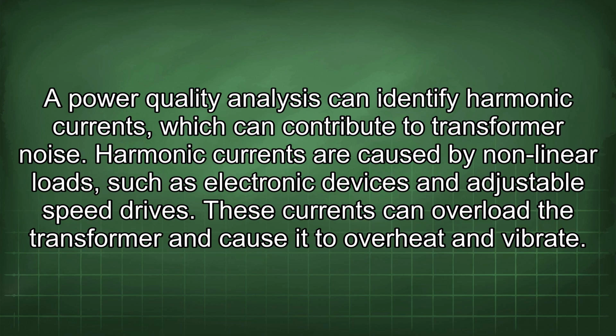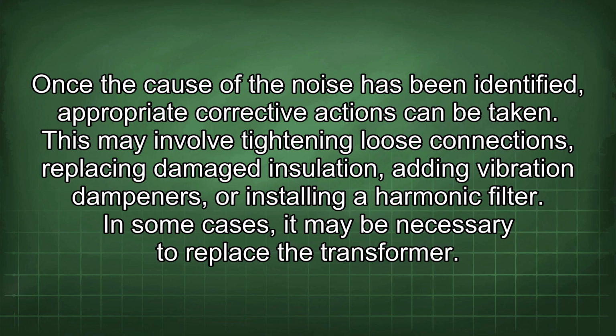Harmonic currents are caused by nonlinear loads such as electronic devices and adjustable speed drives. These currents can overload the transformer and cause it to overheat and vibrate. Once the cause of the noise has been identified, appropriate corrective actions can be taken. This may involve tightening loose connections, replacing damaged insulation, adding vibration dampeners, or installing a harmonic filter. In some cases, it may be necessary to replace the transformer.